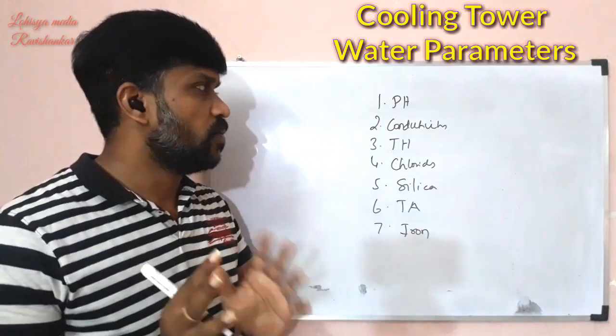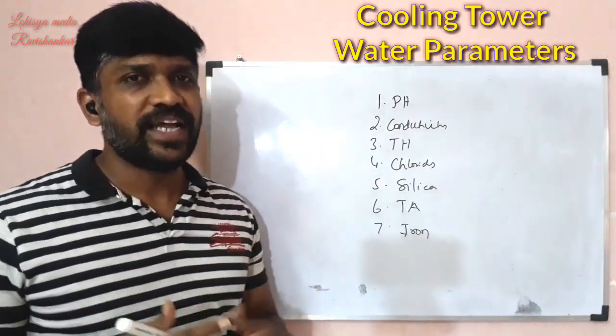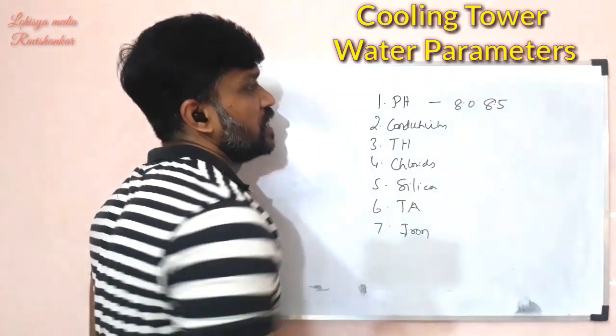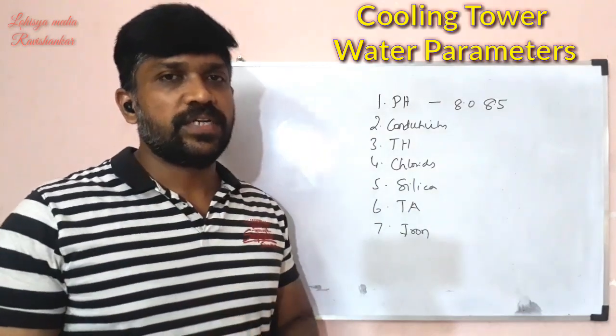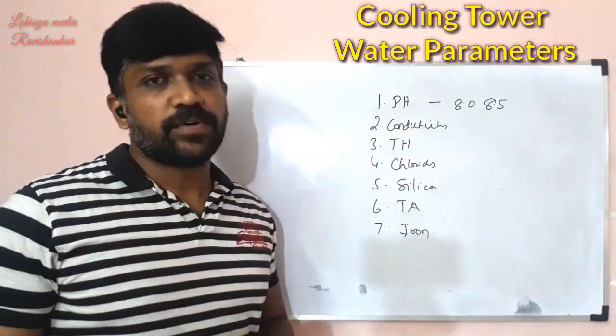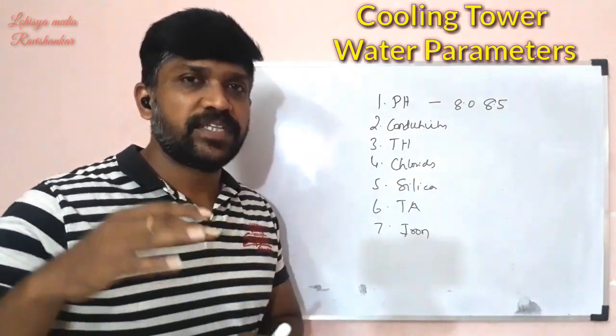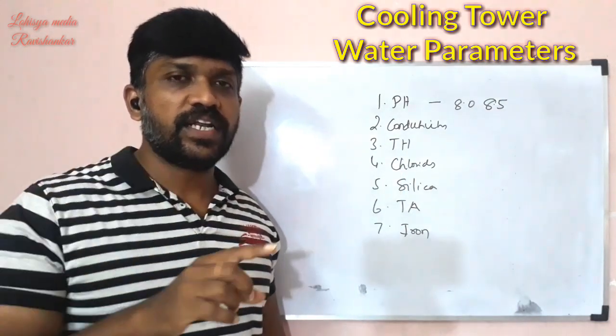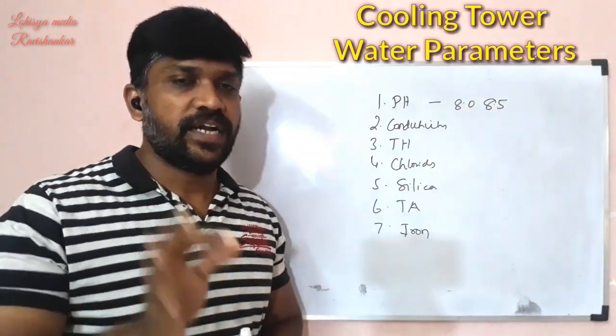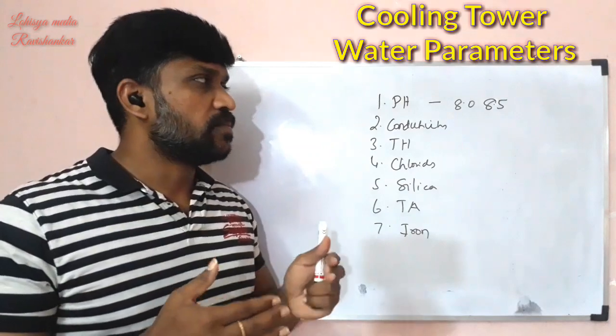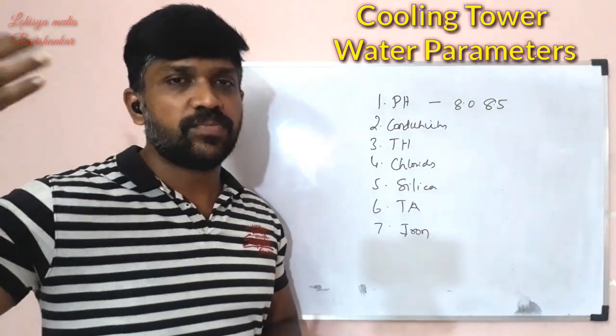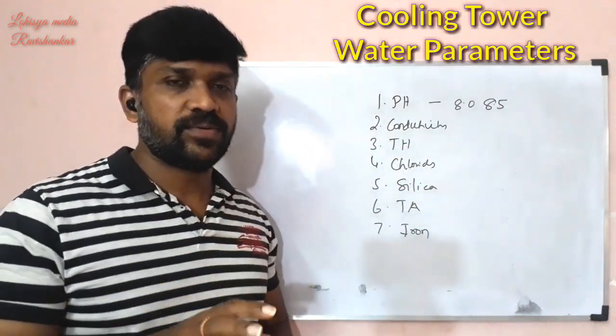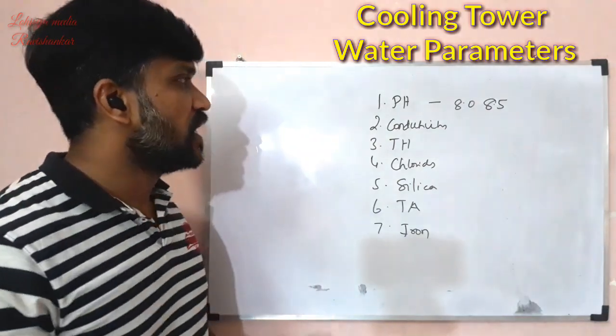For the cooling tower, there are various values and ranges. The pH value maximum is 8.5. We can maintain this cooling tower. pH stands for potential hydrogen. A pH of 7 is neutral on a scale of 0 to 14. Below 7 is acidity and above 7 is alkalinity. If the pH is too low, it indicates acidity and increases corrosion.